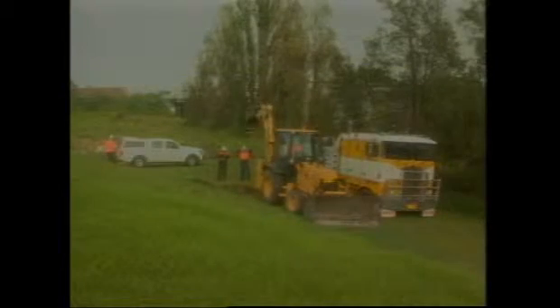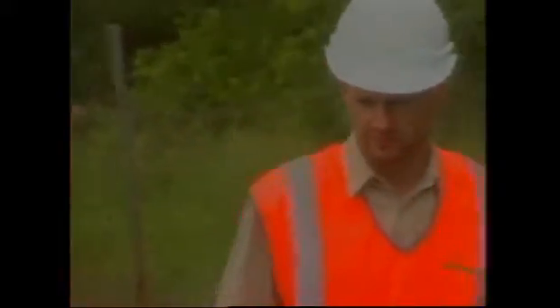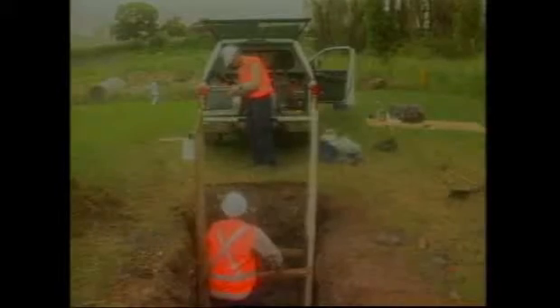Geotherm specializes in thermal property analysis, assessing beforehand the thermal properties of an underground cable's prospective environment. First of all, in thermal route surveys, testing the proposed route at regular intervals. Geotherm, utilizing technical developments from the international leader, Geotherm Incorporated of Canada, has taken the guesswork out of soil physics, and notably that of soil thermal resistivity, or TR as it's known.